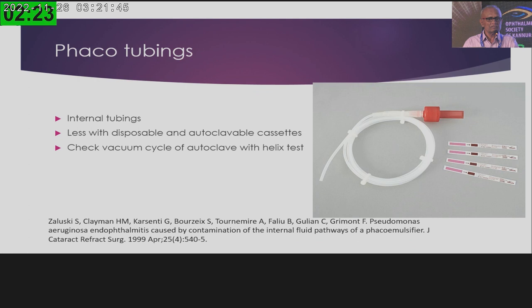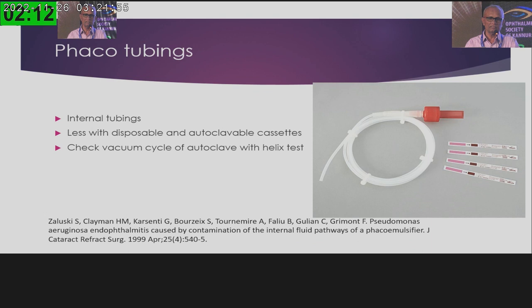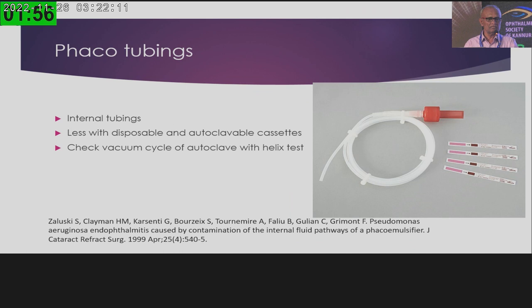For phaco tubings, when using recyclable tubings it is very important to perform the Helix test. The Helix test uses a tube of 1.5 meters length with an indicator container at the end. You run one autoclave cycle with this device — if the indicator confirms the process is complete, you can assume that the vacuum cycle of your autoclave machine is functioning properly.